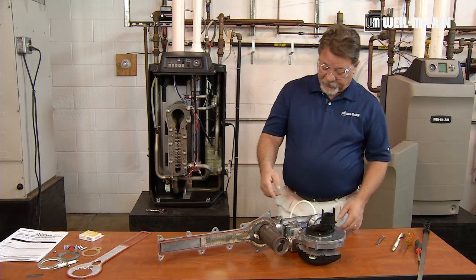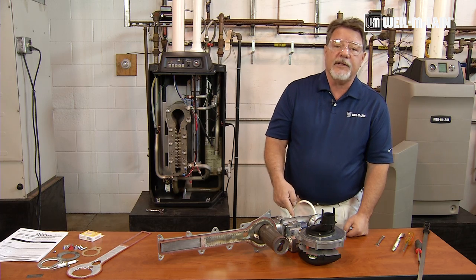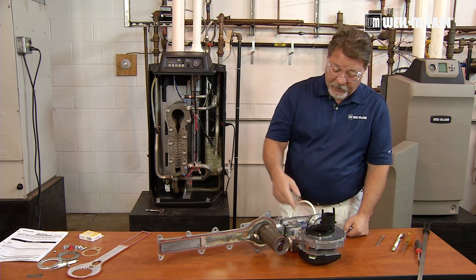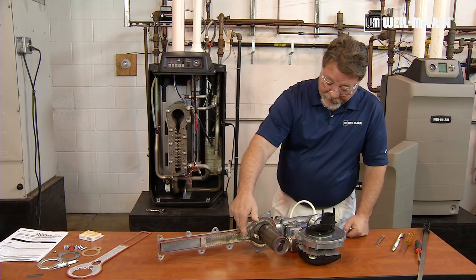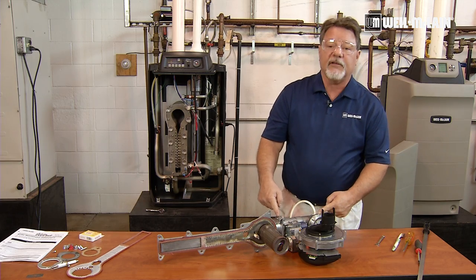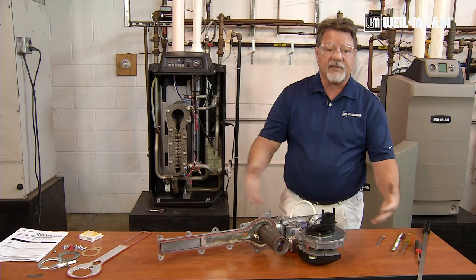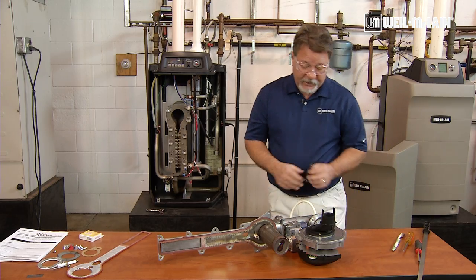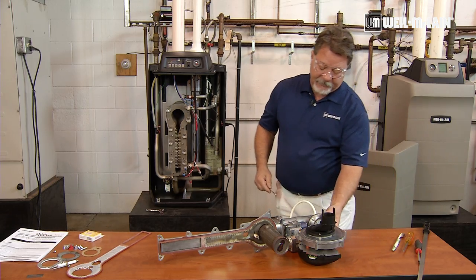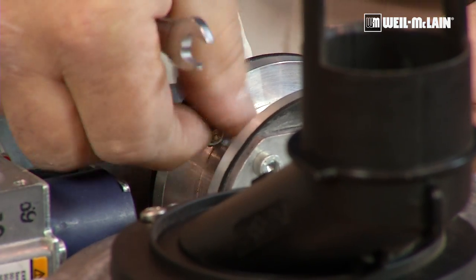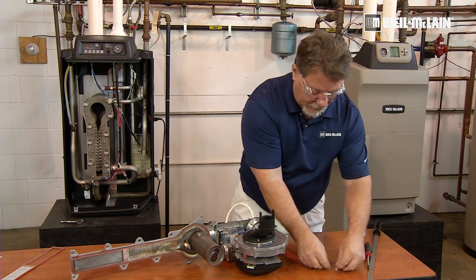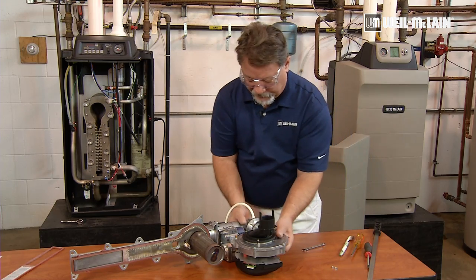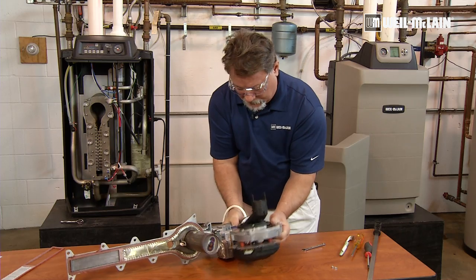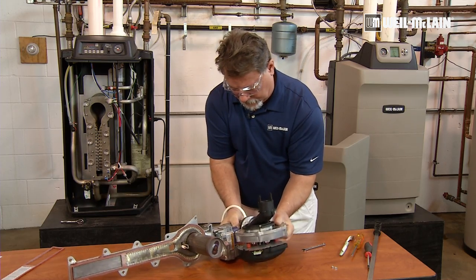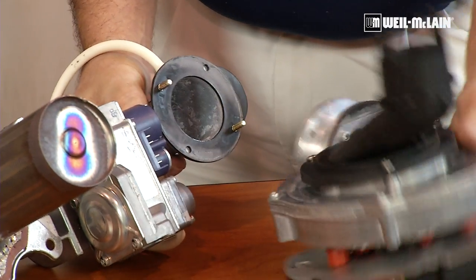What do we need to service? We need to clean the venturi, which is inside here. We need to clean the burner, replace the gaskets in these locations. So we have to disassemble this. I'm going to start with the blower to the adapter block. Now I have two 8mm nuts here. Remove the nuts from the studs that are in the 90-degree elbow, and then separate the blower from the adapter.